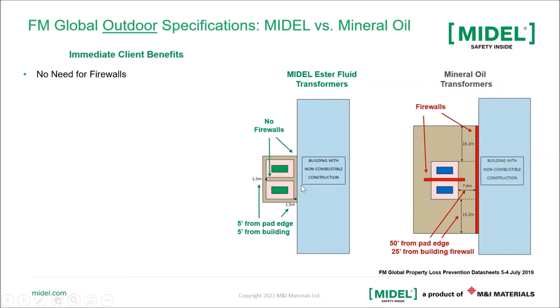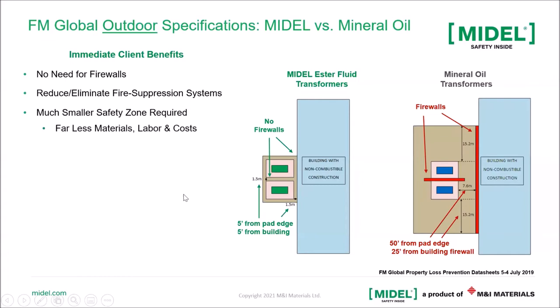So what are some of the immediate benefits? One is that the firewall would not be required. That means that you're saving money in the cost of installing a firewall. The other thing is that there may also be a possibility of removing the fire suppression system. We have case studies around the world where a deluge system or a sprinkler system is not placed over the transformer because the utility or the end user doing the study was able to justify that by removing the sprinkler system, they were still able to eliminate the fire hazard. So there would be a much smaller safety zone as well. And what all that would really mean is that less material would be needed, less cost as far as labor and material, and less real estate. Because the containment is much smaller, the area around the transformer can be used for other applications. And there'll be more details on this in a case study or two.